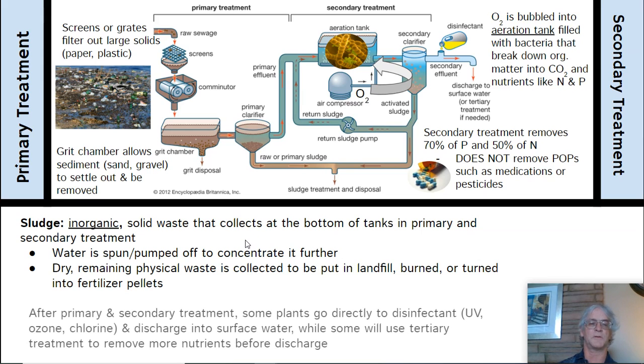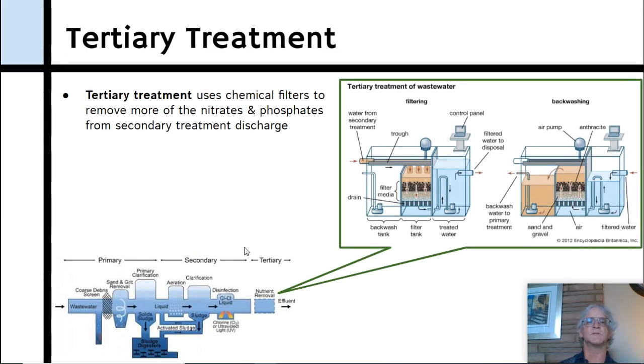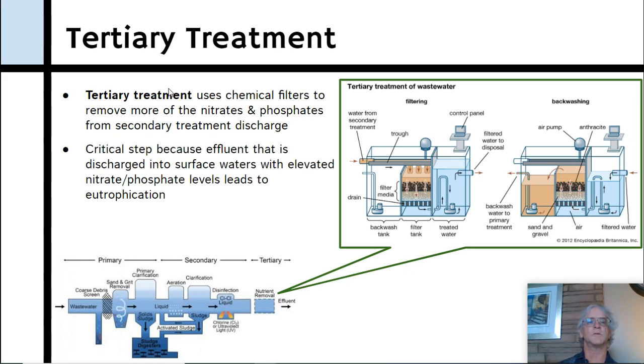After primary and secondary treatment, some plants go directly to disinfection — such as ozone and chlorine — and discharge into surface waters, while some use tertiary treatment to remove more nutrients before discharge. Hyperion unfortunately just does UV, ozone, and chlorine. Tertiary treatment uses chemical filters or plain filters to remove more nitrates, phosphates, viruses, and bacteria. The critical concern is that effluent discharged into surface water with elevated nitrogen and phosphate levels leads to eutrophication. Tertiary treatment is expensive and not always used.